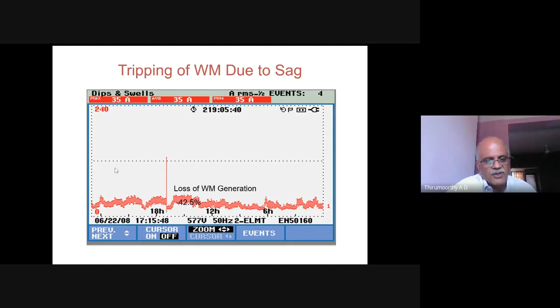So this is actually a case study of transients. Mostly capacitor banks and switched capacitors are used in renewable energy generators also, to make good the reactive power requirement. Generally, nearly 80% of the windmills, especially in Tamil Nadu, are induction generators. Induction generators typically draw reactive power from the grid and supply the active power. So of late, when a larger quantum of windmills got added to the grid, the regulators and grid operators insisted on having capacitor banks at their site so that they don't draw reactive power from the grid.